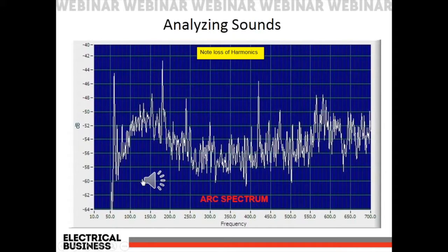Okay, and with that, you can obviously hear that there's a lack of ionization occurring now, where in the last two discharges we heard ionization, but all we're hearing now are the discharges. So that's a big key indicator of sound analysis. But as we look at the spectrum, we start to see the loss of harmonics again, much like with tracking. So we're not seeing 60 hertz showing up, but we do have content in between our harmonics. Just they're not evenly spaced like we saw before in some of our other electrical emissions.